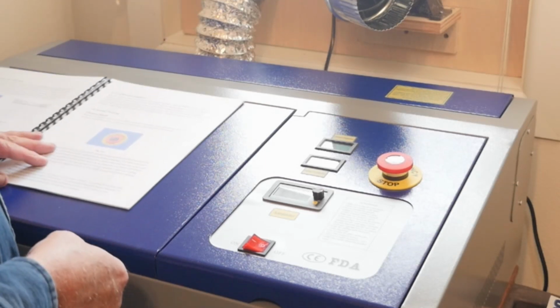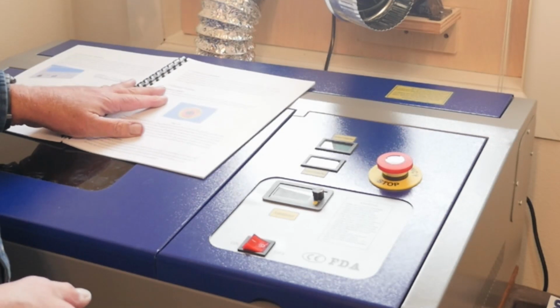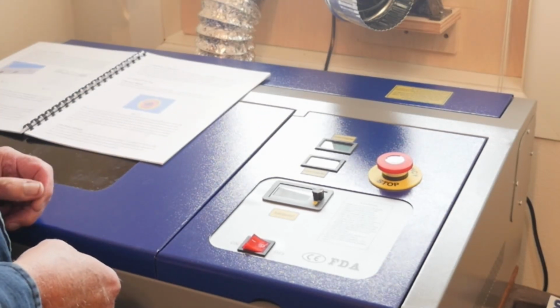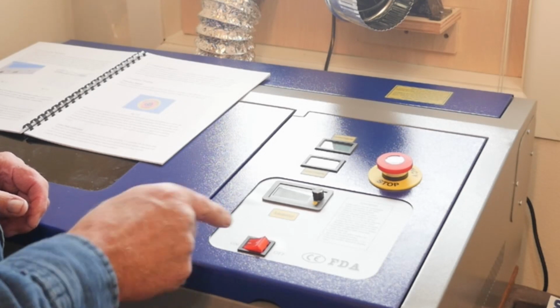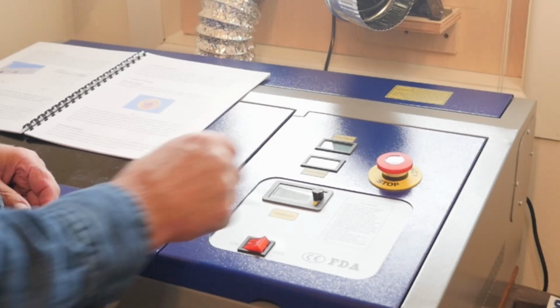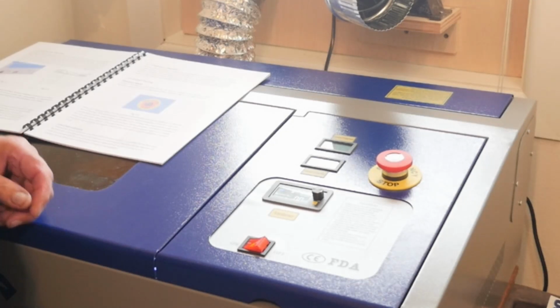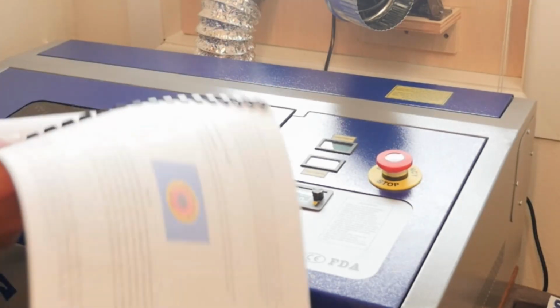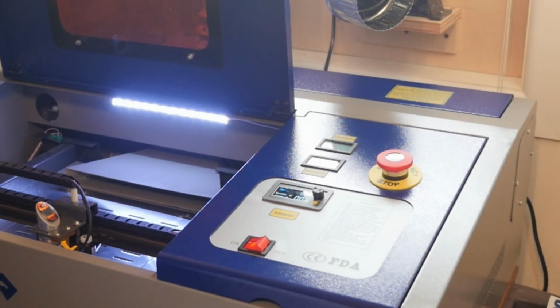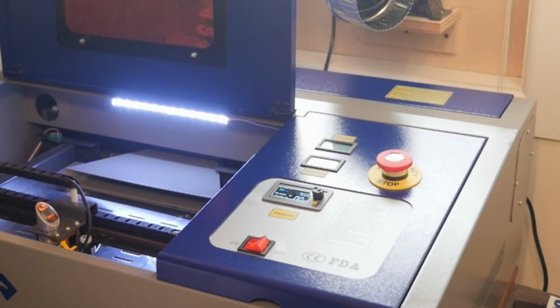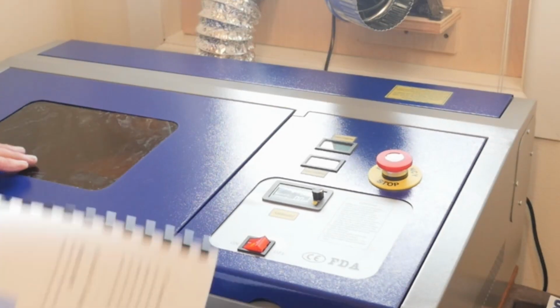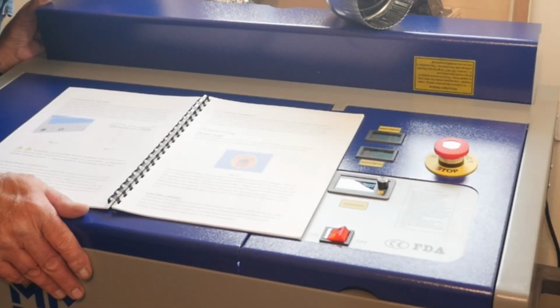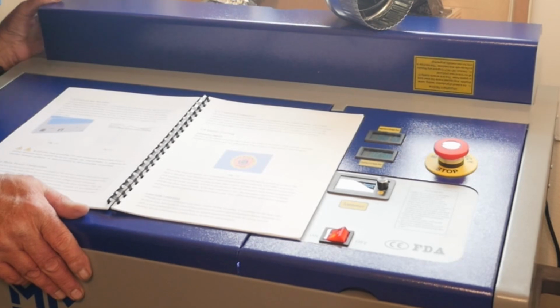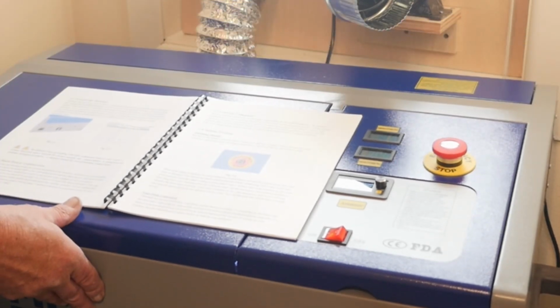So the first thing we need to do here, and I'm going right by the manual, is the emergency stop check. So turn this on - it doesn't do anything because right now the emergency stop is tripped. Release that, and I hear the fan coming on. My little light came on inside. And I need to look in underneath and make sure the water is circulating - and it is, with no air bubbles.